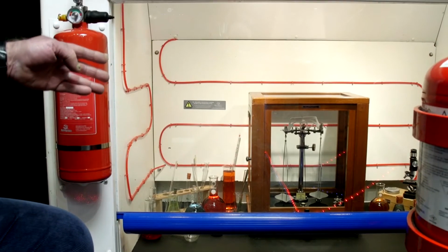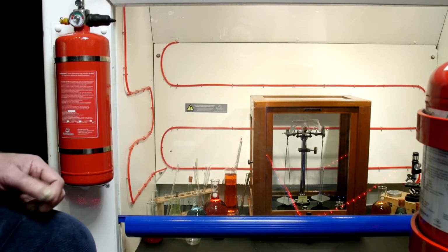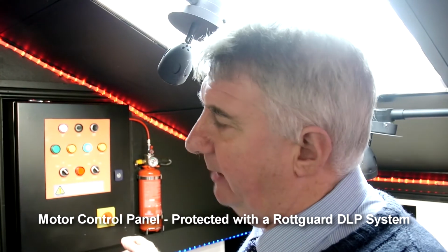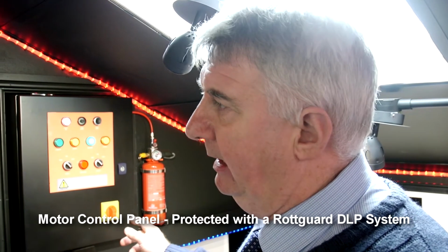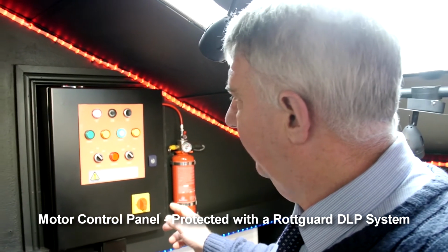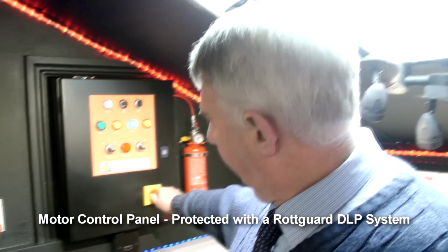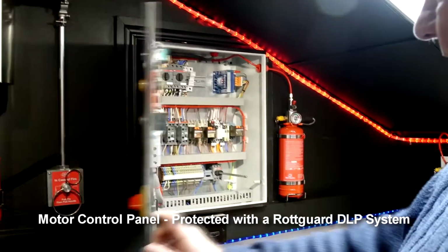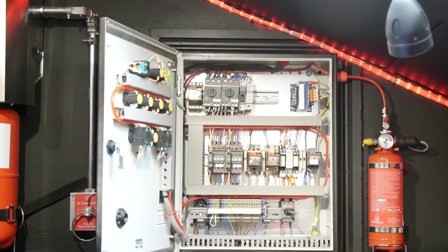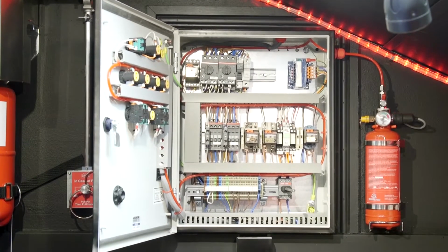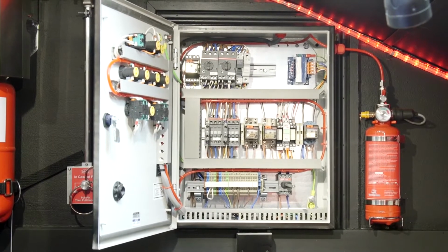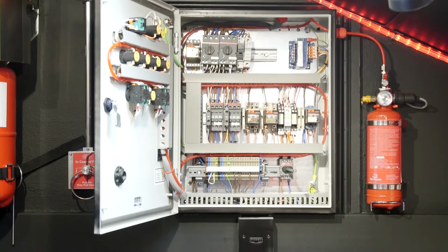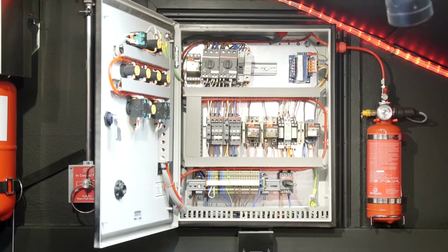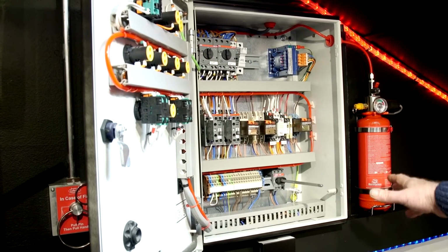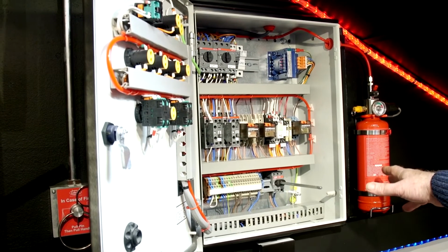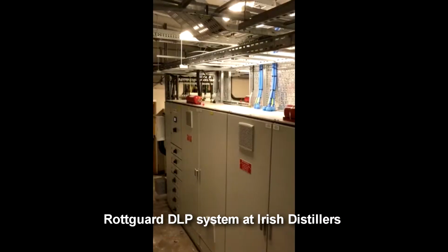The tube will again rupture in the same way as we'd seen in the electrical application. This is an example of a Rottguard DLP system in the manner in which it would protect a motor control cabinet. If we look at the inside, you'll see all the various switchgear components. We have contactors, circuit breakers, a transformer, all the rail terminals and relays. We're using a small cylinder in this instance to protect this enclosure.